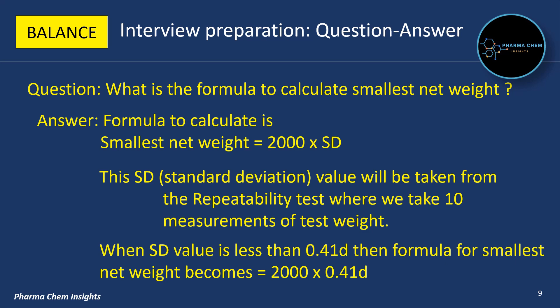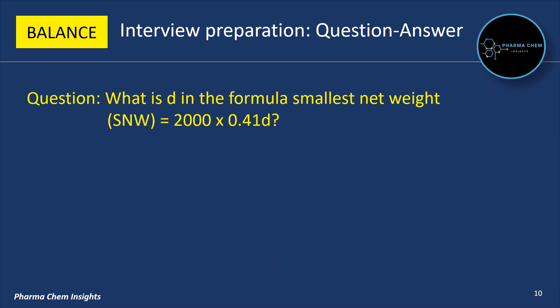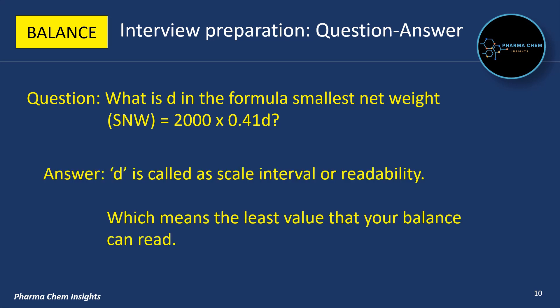When the SD value is less than 0.41D, the formula for smallest net weight becomes: SNW = 2000 × 0.41D. Here, D is the scale interval or readability, which means the least value that your balance can read.